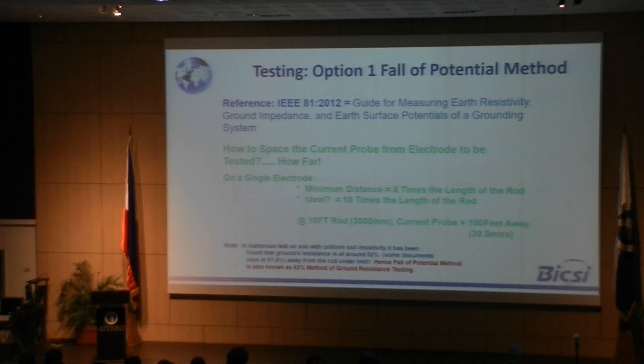When testing, for a 10 foot rod, the current probe should be 100 feet away, or 30.5 meters. That's also your farthest test rod equipment, that's the current probe. In the standards, to be faster, in case of rain and everything, they say you can just go to 62% of the distance for your test probe, but don't trust it.